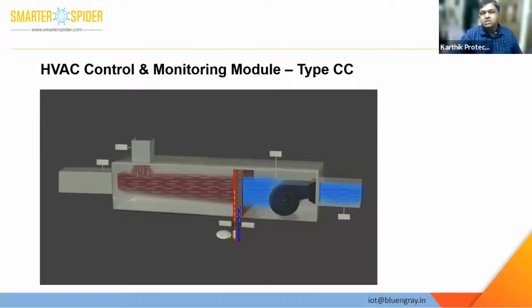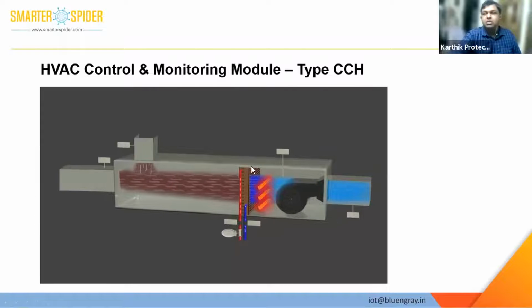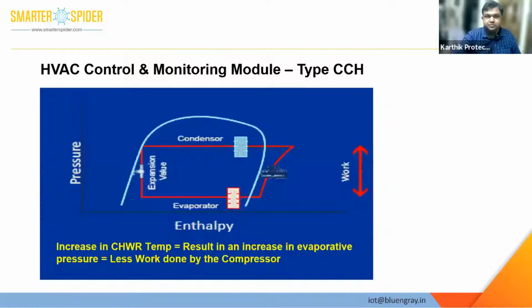Now coming to the simulation, this is a typical chill water type AHU where we have a sensor at the supply air, measure the delta P from our duct pressure, then we have temperature sensors for chill water supply, chill water return, return air, as well as fresh air and mixed air. And this is a type of AHU for applications where you want to maintain humidity levels inside the room. So we have a heater control facility also. This simulation is for an electronic heater, whereas if you have a hot water system running through the AHU, we can modulate the hot water actuator also.